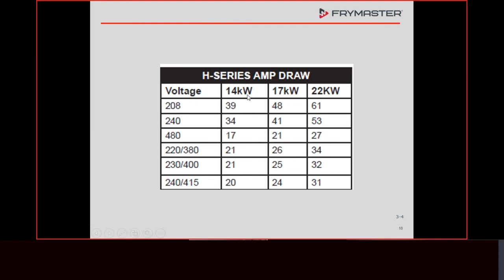That's satisfactory as far as doing an amp draw during a startup or troubleshooting. We want to make sure that every wire has amperage on it when it's calling for heat, and every wire is at 0 when it's not calling for heat. But this right here is the chart if you are able to get a 3-phase amp draw. This slide, actually, I jumped ahead a little bit because this is the same one that we had before. I was going to mention all the other stuff internally. This is where I was going to start talking about the inspections. So I jumped ahead a little bit.